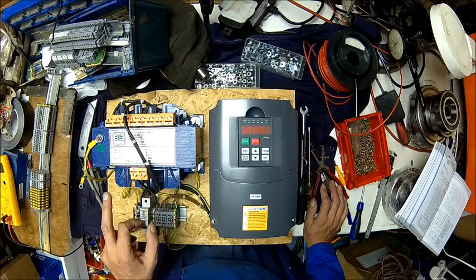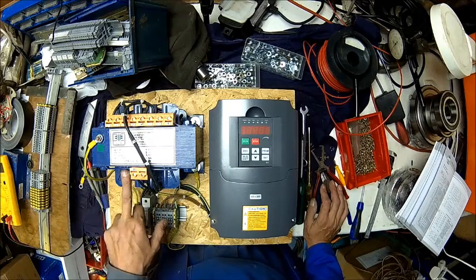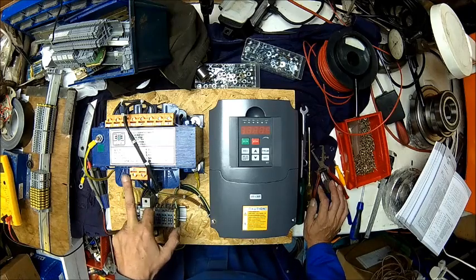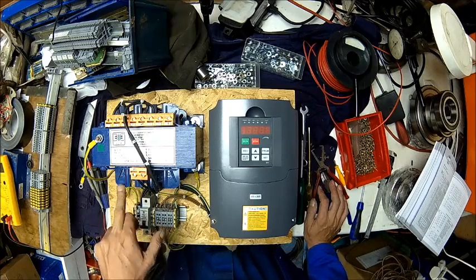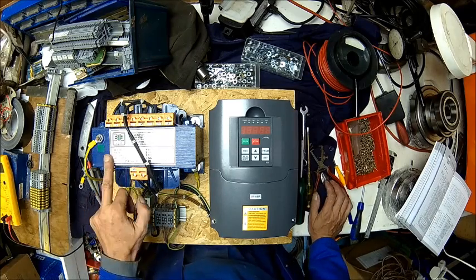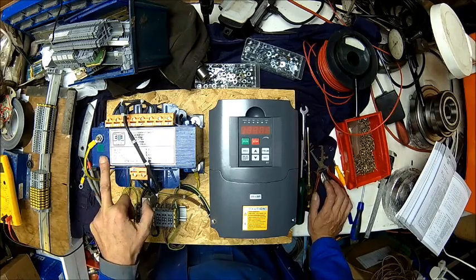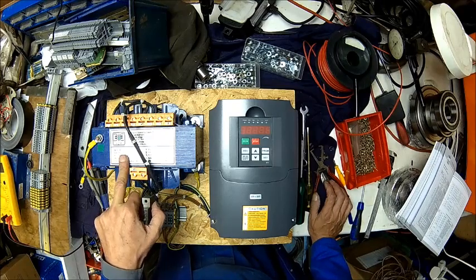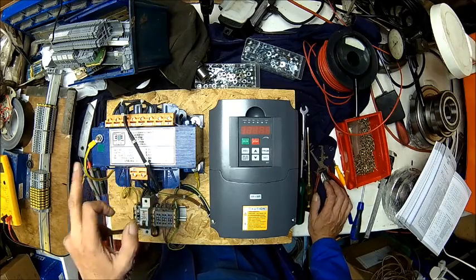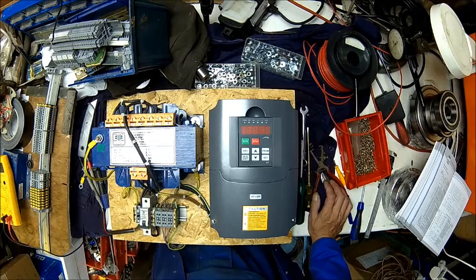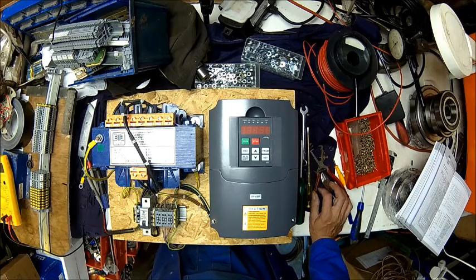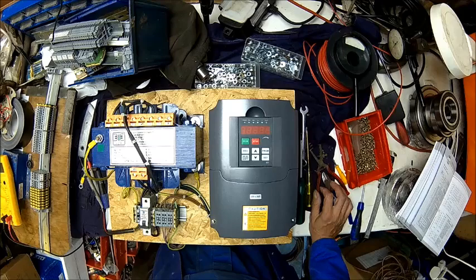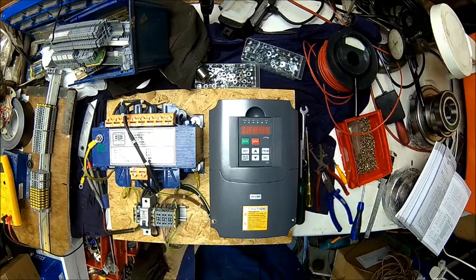The only thing you need to make sure is that the transformer is actually good for the insulation of 400 volts. I checked them with 1000 volts and it's fine. These are isolation transformers, that's what they're supposed to be, and it's 2000 VA, that's 2000 watts with a power factor of 1, so it's probably 1.8 kilowatts, because this thing is producing a bit of power factor here. I need to check what voltage setting he wants, but I think he said 415.